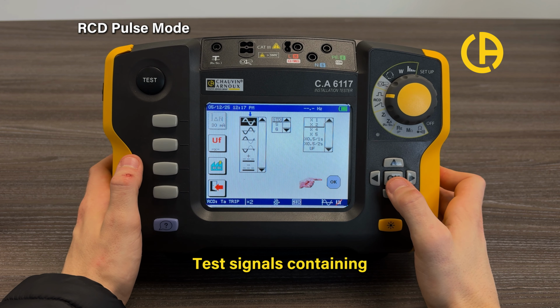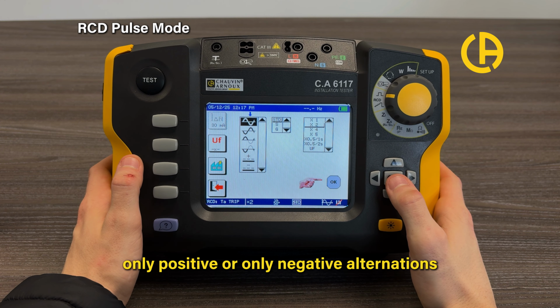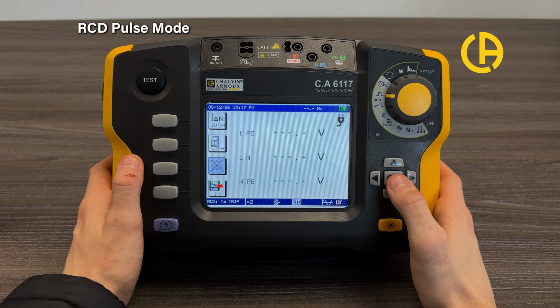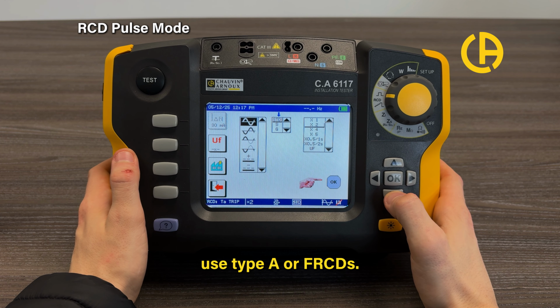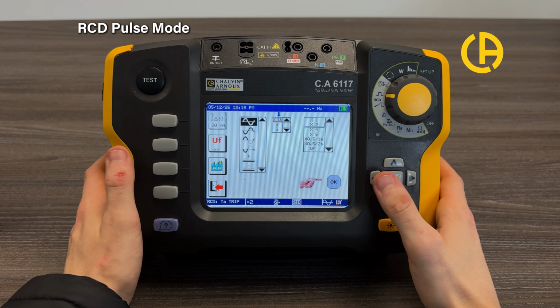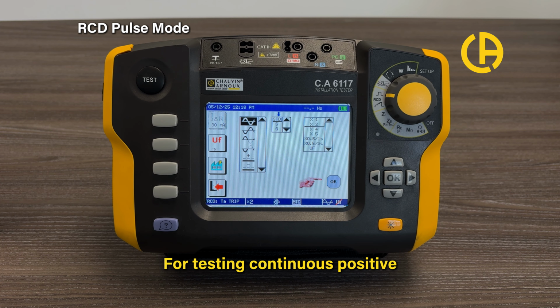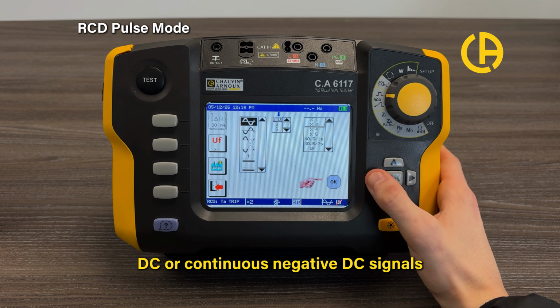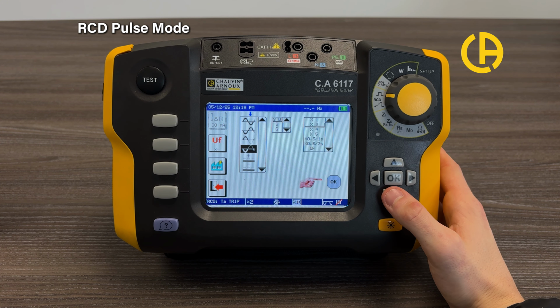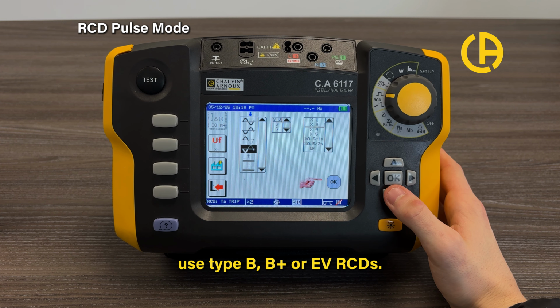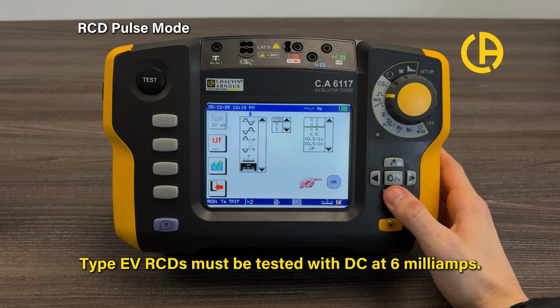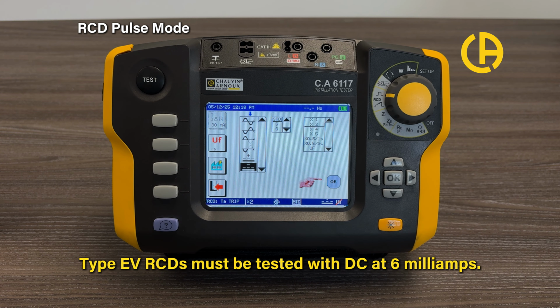Test signals containing only positive or only negative alternations use type A or F RCDs. For testing continuous positive DC or continuous negative DC signals, use type B, B+, or EV RCDs. Type EV RCDs must be tested with DC at 6 milliamps.